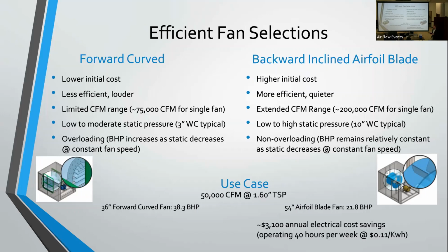That's also an overloading fan. So as your fan speed remains constant and your static pressure decreases for whatever reason, your brake horsepower will actually increase with forward curve fans. So you're overloading the fan and you have the potential to actually overload that motor. Which is kind of a strange, counterintuitive thought, because as that static pressure decreases, you're increasing your brake horsepower. So that's one bad thing about the forward curve fan design.